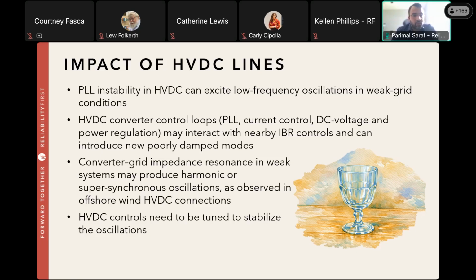HVDC lines have been used to transport power into the electric grid, and those HVDC lines have been shown to demonstrate supersynchronous oscillations, which is essentially, again, resonance between the offshore wind farm and the electric grid. It's very similar to a subsynchronous resonance kind of phenomenon, basically the grid resonating against the wind farm. HVDC lines have also demonstrated that oscillatory behavior. In the end, HVDC controls can be tuned, and need to be tuned, to stabilize these oscillations. So these oscillations can be stabilized, but it involves tuning the controls installed on the HVDC lines.